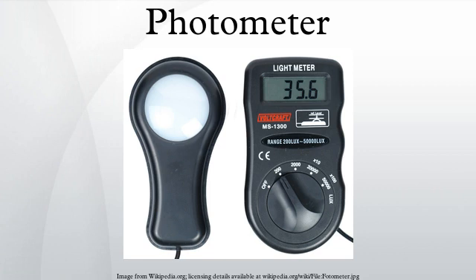UV and visible light transmission photometers are optical instruments for measurement of the absorption of light of a given wavelength of colored substances in solution. From the light absorption, Beer's law makes it possible to calculate the concentration of the colored substance in the solution. Due to its wide range of application, reliability, and robustness, the photometer has become one of the principal instruments in biochemistry and analytical chemistry.